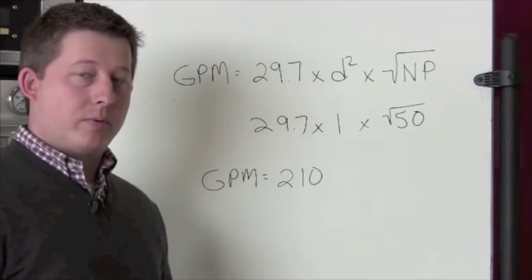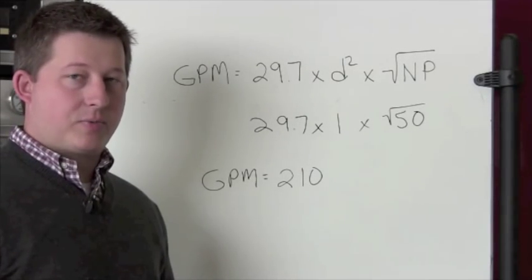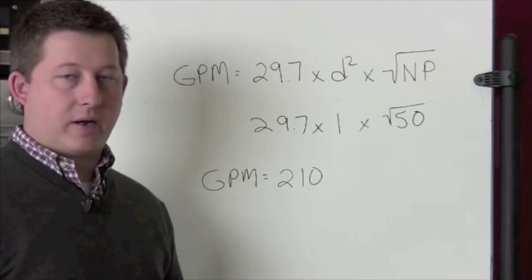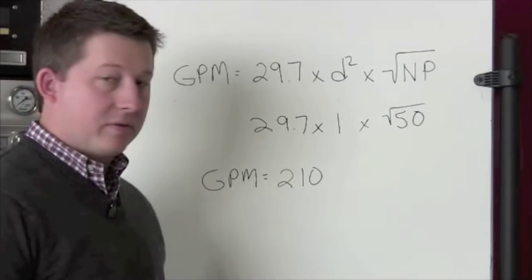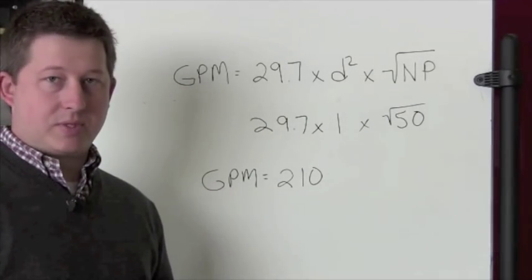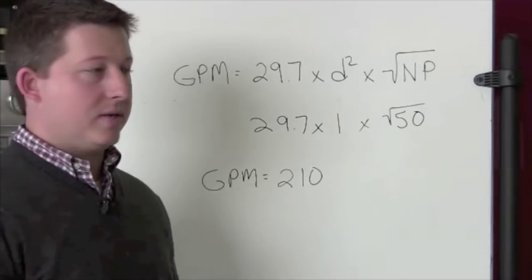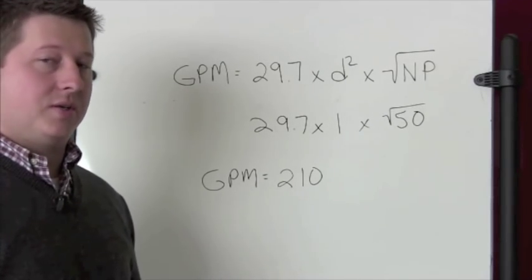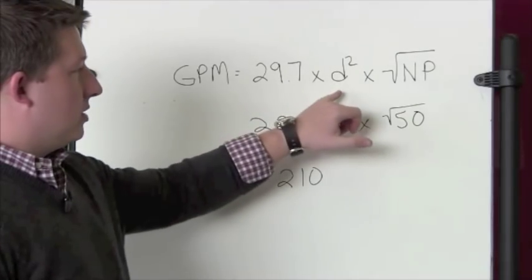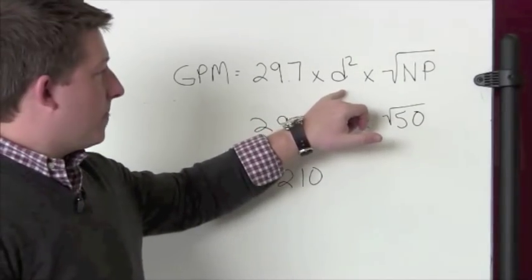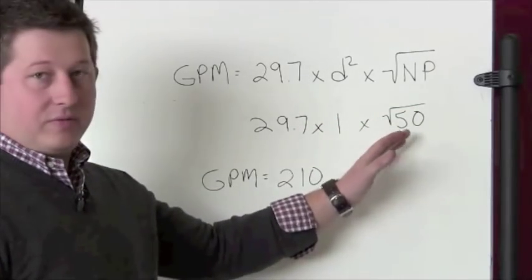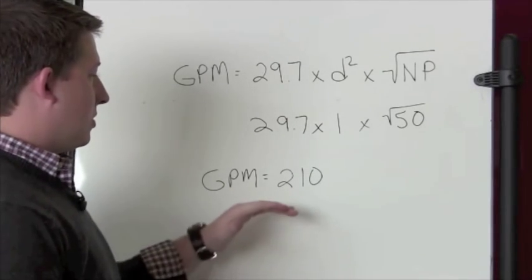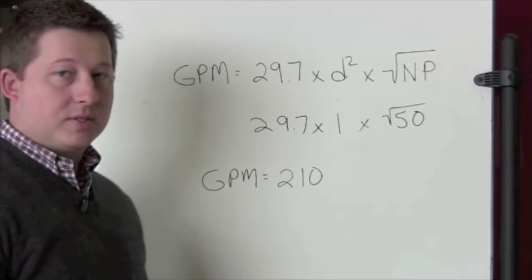I'm going to do the exact same formula, but instead of using 80 psi for nozzle pressure, I'm going to change it to 50 psi. So we're saying we're using a one inch nozzle on a handline, basically like a high rise pack. Using it as a handline instead of a master stream, the only thing we change is the nozzle pressure. So it's 29.7 times diameter squared — one inch tip — times the square root of 50. Working the problem out, 29.7 times one times the square root of 50 gives us 210 gallons per minute.